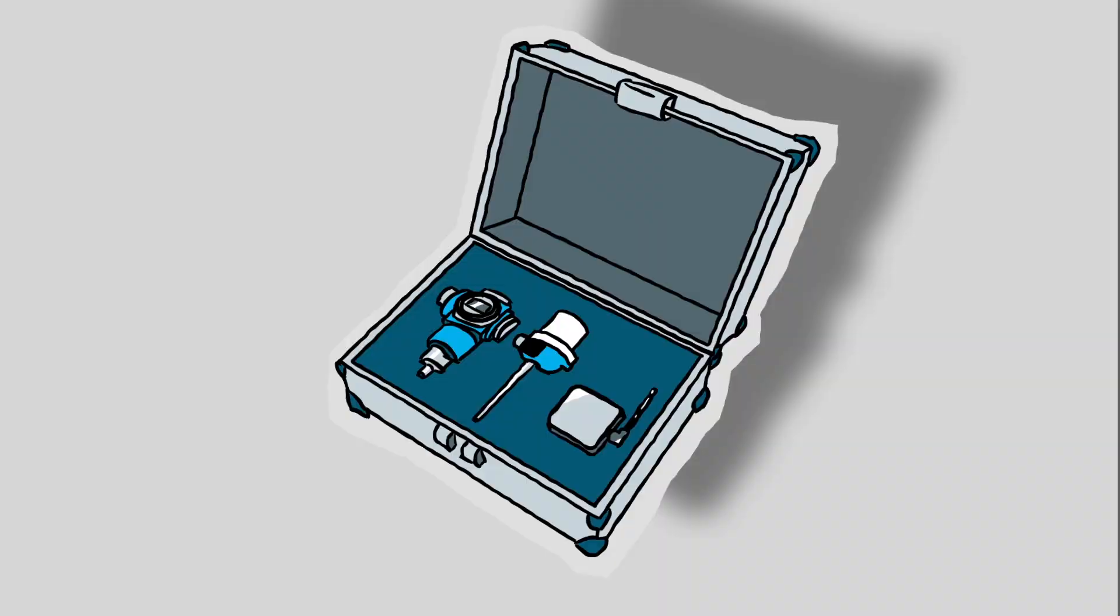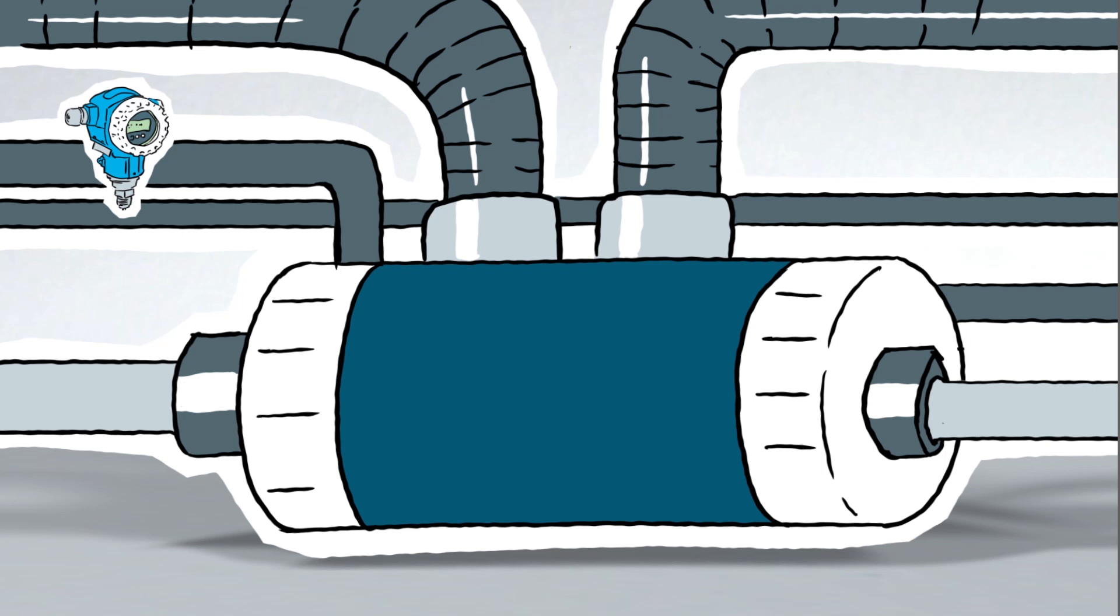By using Endress+Hauser's pressure transmitters, the entire process pressure monitoring in the denitrification unit can be partitioned and delimited. Differential pressure measurements can be made at several locations, which simplifies the detection of scaling. And the efficiency of the heat exchanger can be easily monitored by using temperature transmitters.